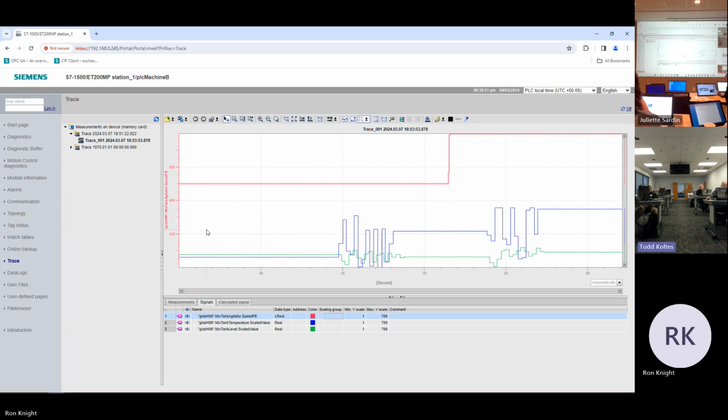As end users, this is your maintenance guy with any laptop. Plug into the PLC, doesn't need TIA Portal, doesn't need to manipulate code or anything, whether you trust him or her, but so easy, even sales guys can do this. Yeah, just connect up, open Chrome, type in the IP address, and they can see what you've allowed them to see here. From a troubleshooting standpoint, most of the time it should get them where they need to go. And even from the web server, you can grab this data and save it out as a CSV file on whatever device you're accessing it through.